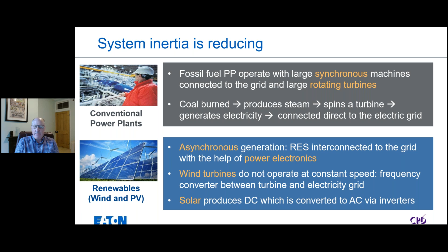You might think that the spinning blades in those turbines would carry a large amount of inertia. But of course, because the speed of the wind varies, so does the speed that the blades rotate at. So they have to go through a DC link, and there's then a converter to change that DC into AC to synthesize a 50 Hertz grid frequency and to synchronize and connect to the grid. Similarly, solar PV is native DC technology. So again, that has to go through an inverter to synthesize that 50 Hertz frequency and synchronize and connect onto the grid. So again, that doesn't carry that same inertia that a traditional generator would.